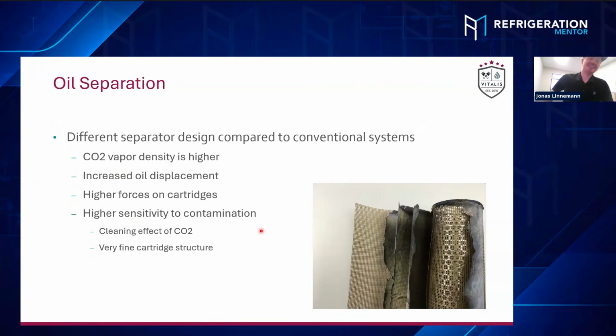I don't know how I should call that. But there are some generally different aspects which apply to CO₂ separators compared to normal separators. As I've mentioned before, the CO₂ vapor here is a very thick gas. Especially in the high pressure discharge line, you sometimes run up to 100 bar. And this gas gets so heavy that the oil drops are not really dropping down.